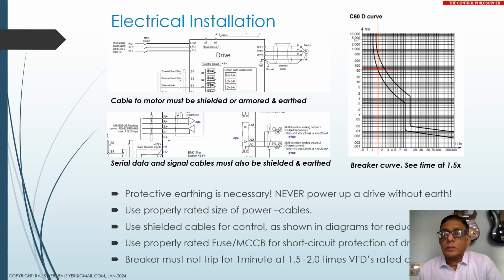Alright, so this is very important for a short circuit because VFDs will draw surge currents from time to time, and especially at startup, when the capacitor will need to charge up. So we have to select it correctly. It is not necessary to select a circuit breaker to protect the VFD against overcurrent. No, the circuit breaker is for short circuit protection alone. Okay, the VFD itself is acceptable as an overcurrent protection device. Right? Okay.